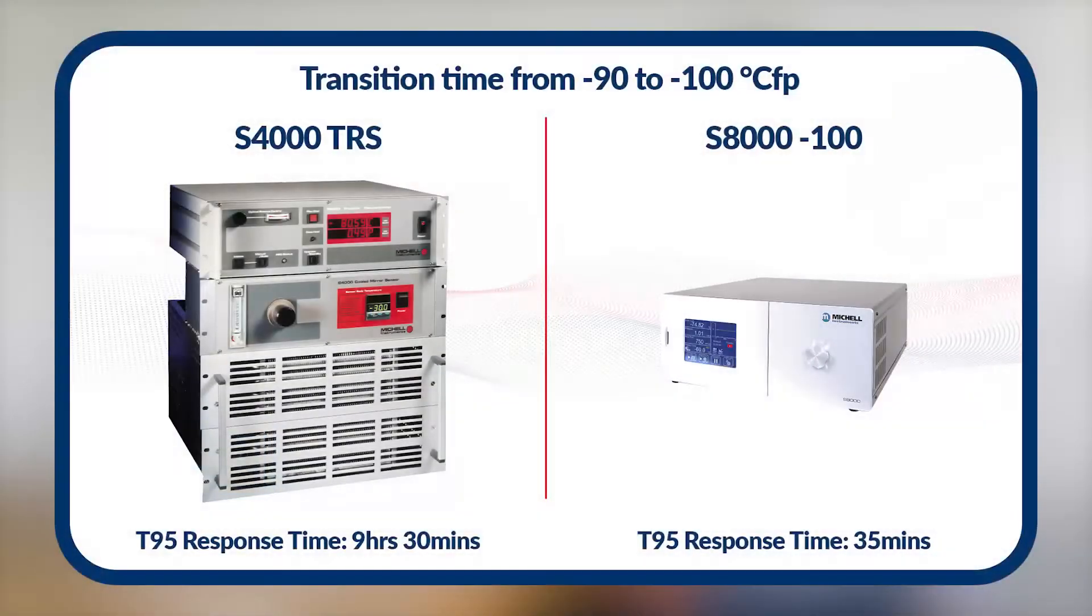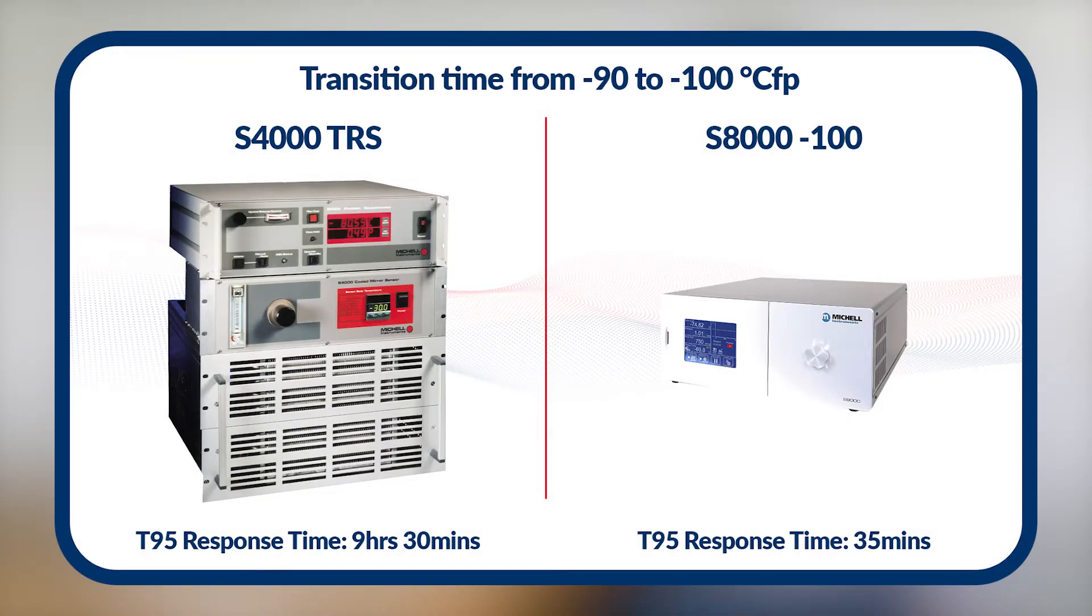As a comparison, for a Michell S4000 TRS, the typical T95 response to a transition from minus 90 to minus 100 degrees frost point is 9.5 hours. The same transition takes the S8000-100 just 35 minutes.